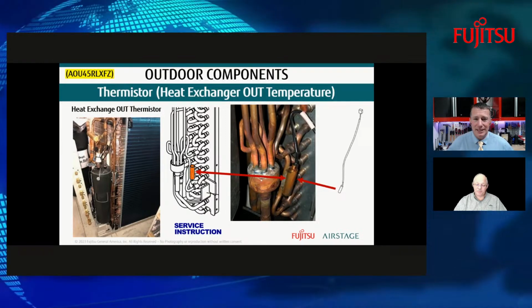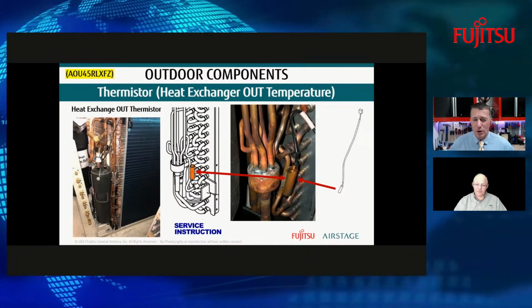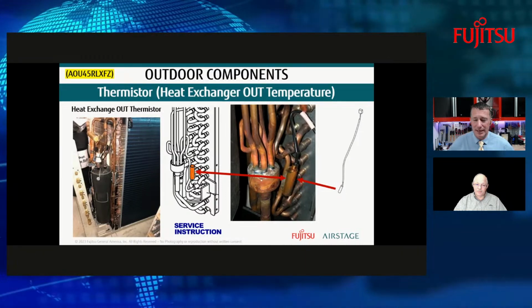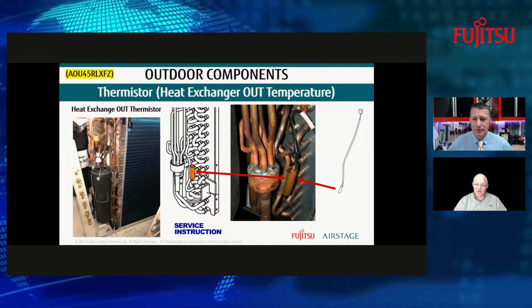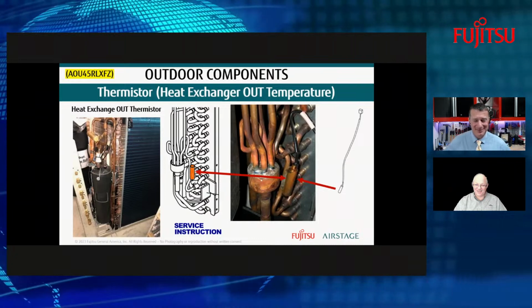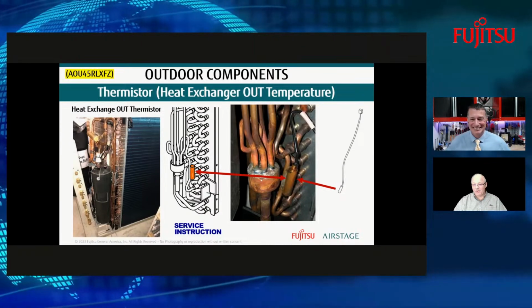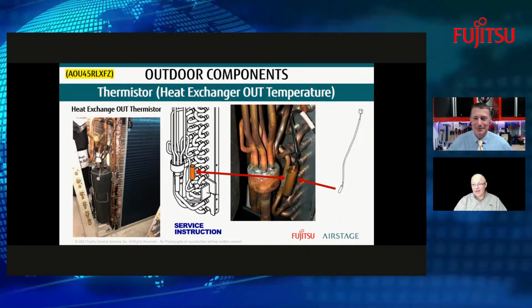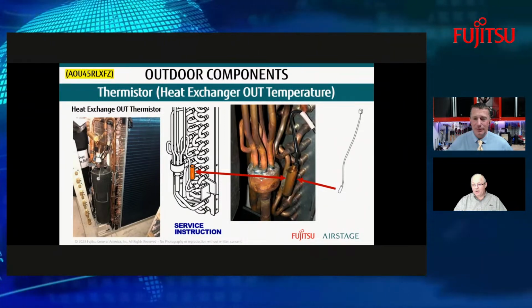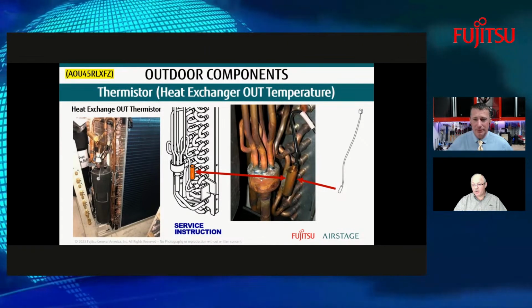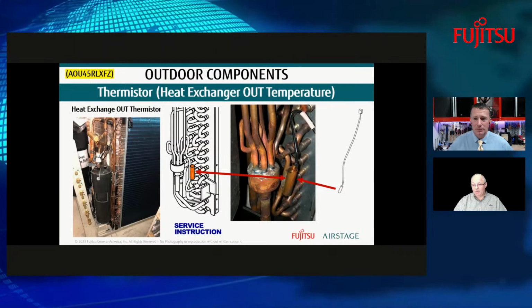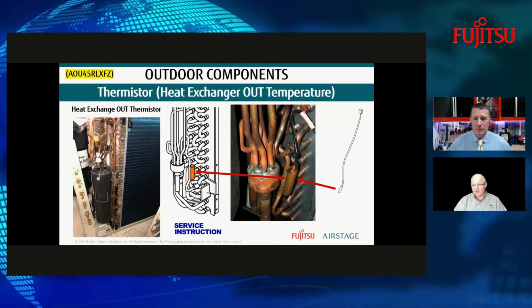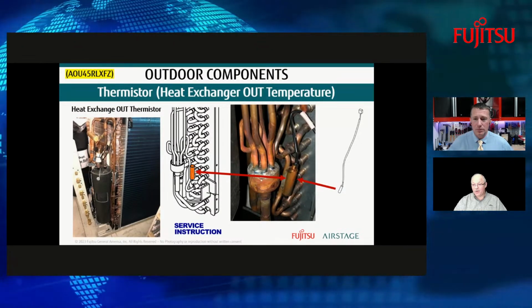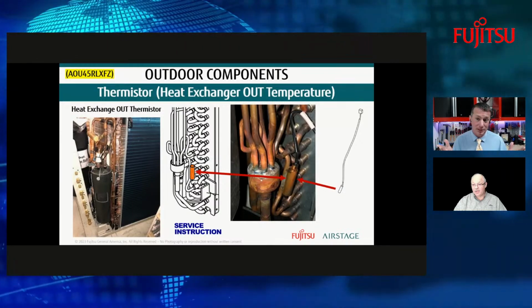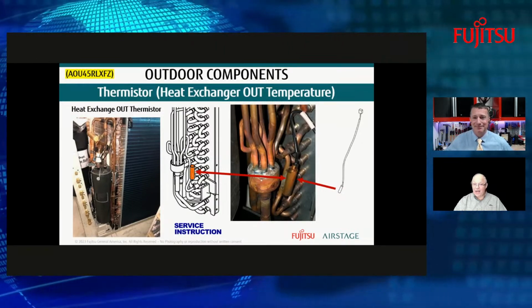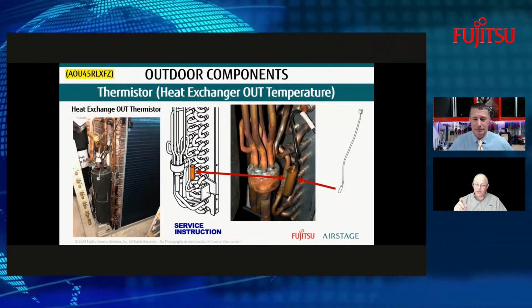So would you say that the heat exchanger thermistor is the primary control for the outdoor fan motor? Now, I'd say it's all a piece of it. Okay. Now, as far as the outdoor fan motor is concerned, again, it's going to speed up depending upon what's happening to the outdoor temperature. Right. So if the outdoor temperature keeps climbing and you go to 100 degrees outside, well, you know that the outdoor ambient thermistor is going to already give its input. That one's already being one of the keys.